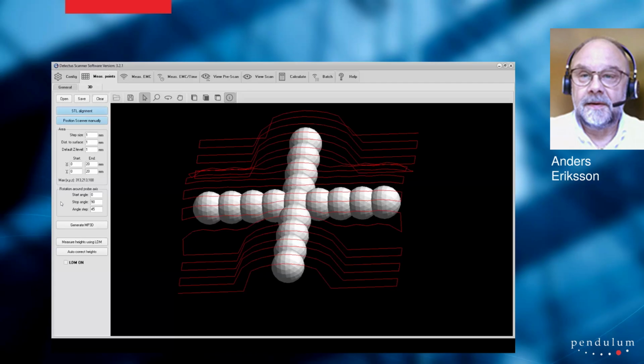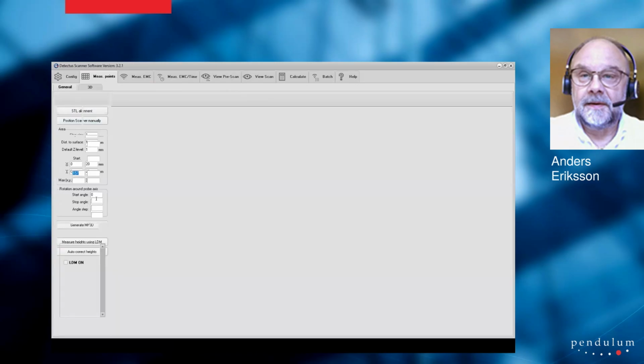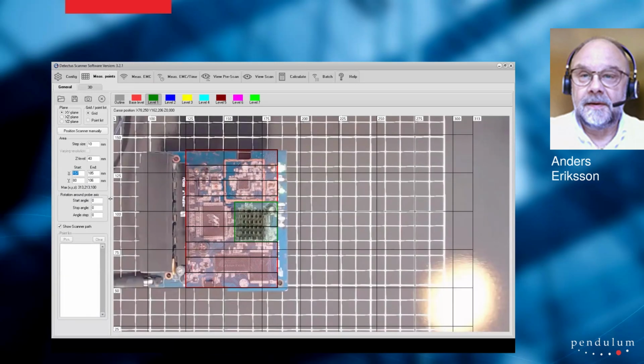You see here rotation around probe axis. If we are using a probe with a vertical loop like this, it makes sense to rotate it in every measuring position so that we get the worst case, and this is done in this area. Same you can do if you do this 2.5 dimensional way of generating the measuring points.